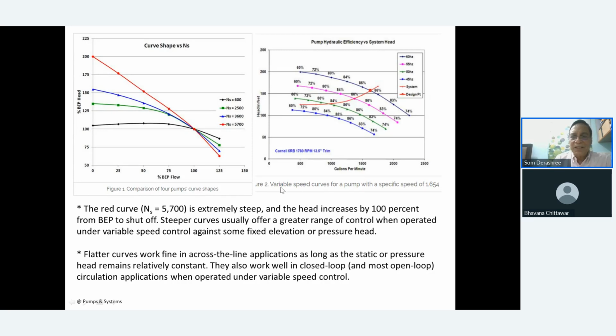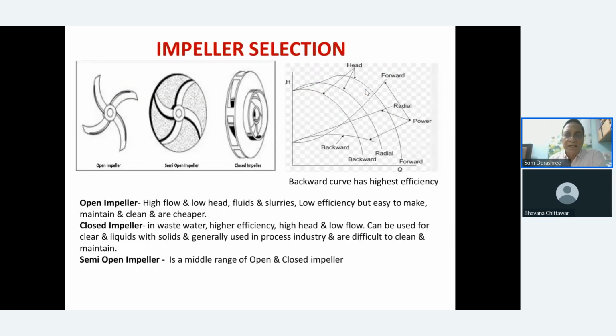This is, of course, a variable speed curve for a pump with specific speed of 1654. So the speed is already given, and then you have these different curves. This is the system curve, and all these are design curves basically, and these are all efficiencies which are tabulated here. This is again gallons per minute versus head flow. So basically, you will find that pump efficiencies are somewhere here, and subsequently we'll come to know how the efficiencies are decided.